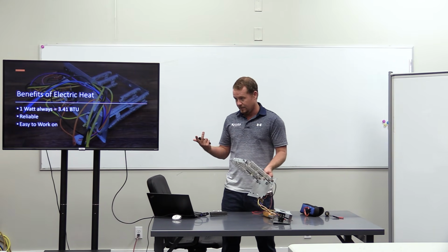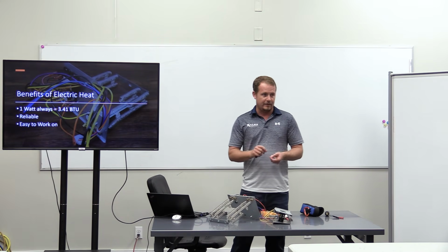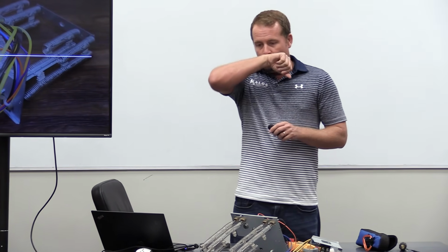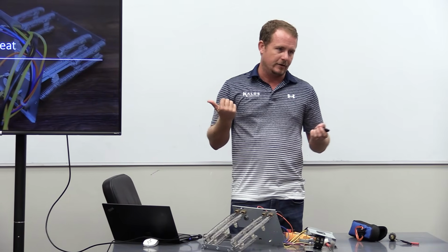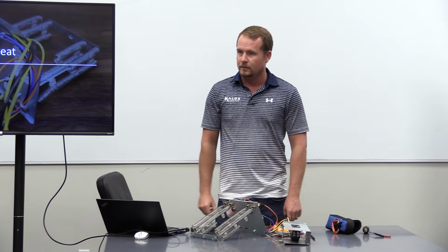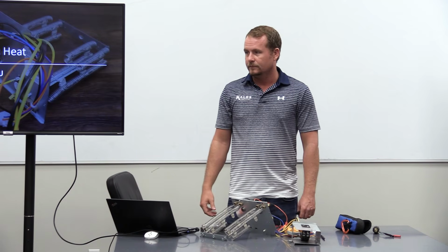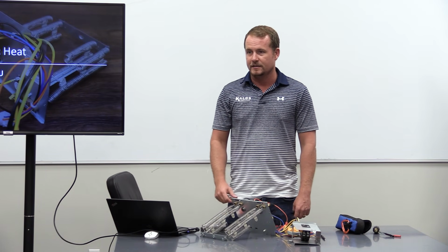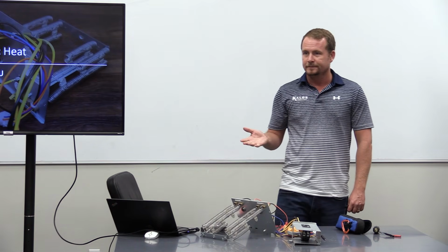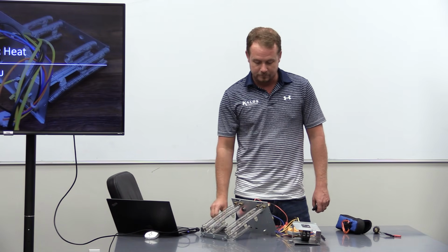It's the first time I'd ever done it. So as you can imagine, I kind of bungled it. As I was making the terminations or whatever, it kind of kinked and like broke, and it was in bad shape. So I thought, well, this customer, it's just heat strips. So if I take a little bit of heat strip off, just a little bit, the part that's broken, that's not going to hurt anything. It just won't heat quite as well, right? Does that stand to reason? Stands to reason that if you take a little bit of heat strip off, it just won't heat quite as well. Does everybody agree with that? It'll still heat, it just won't heat quite as well. Just took a little strip off, right? Okay. Here's the problem with that.